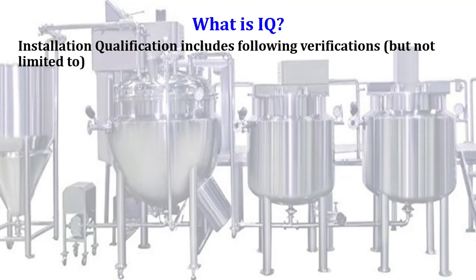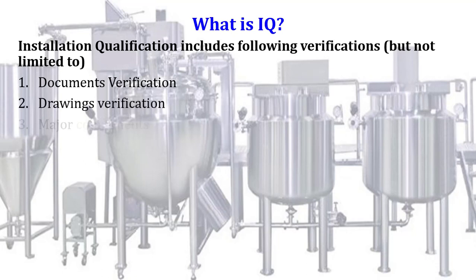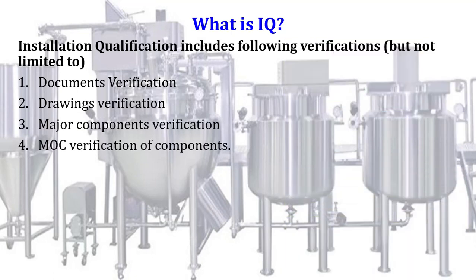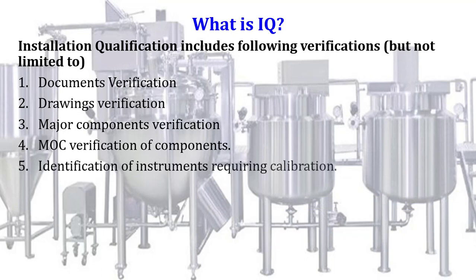Installation qualification includes the following verifications, but not limited to: documentation verification, documents verification, drawings verification, major components verification, MOC verification of components — MOC means material of construction — verification of components.